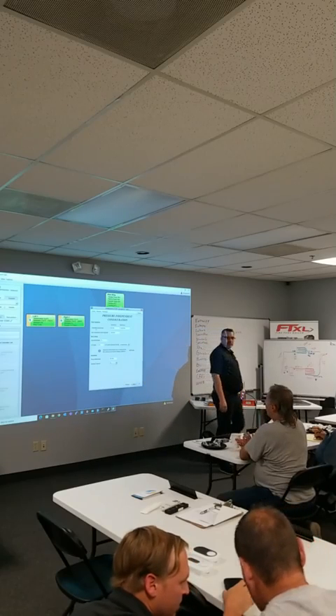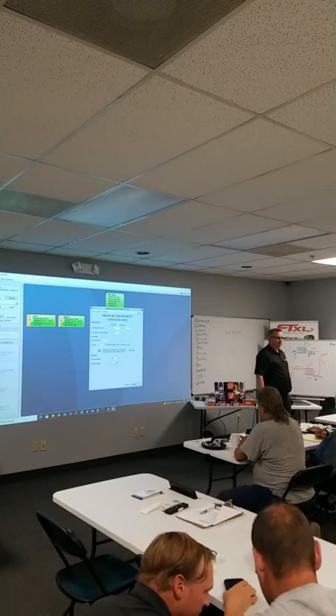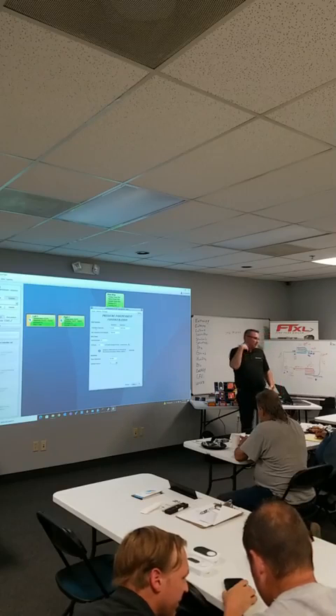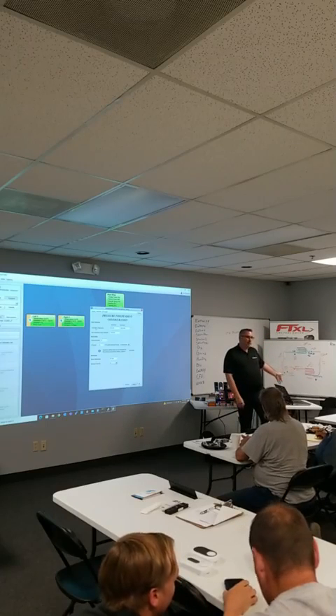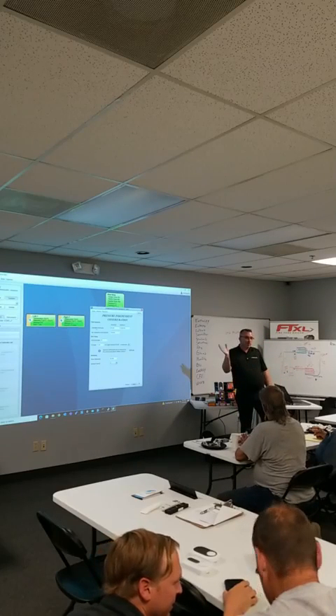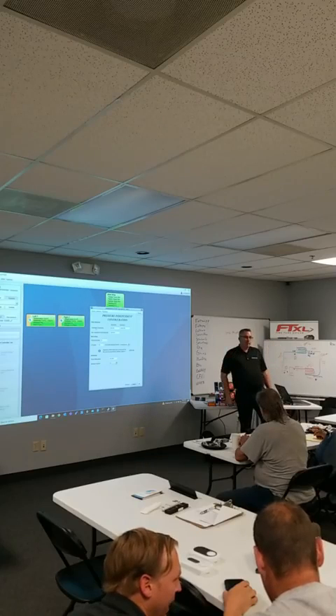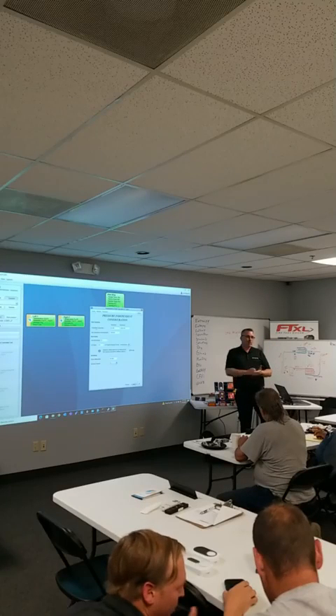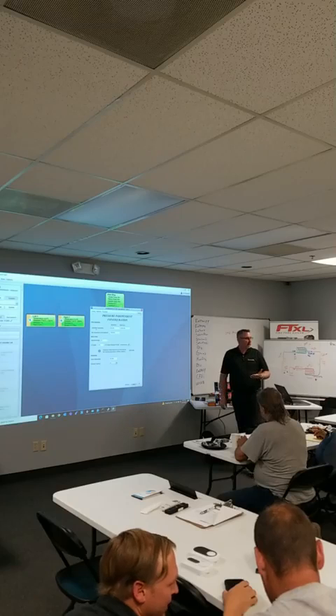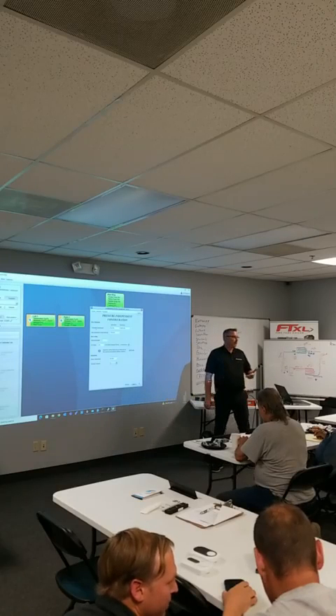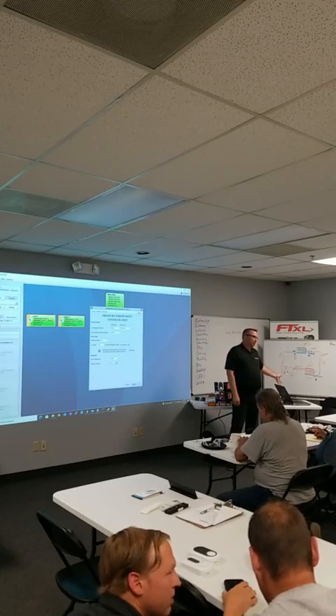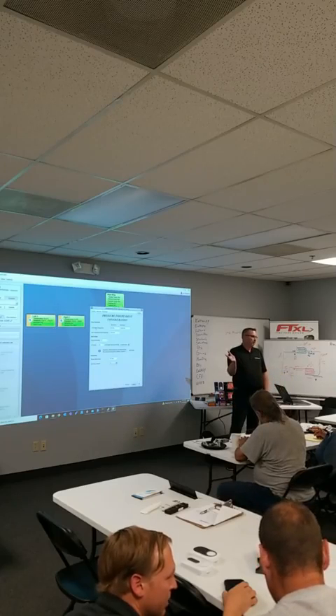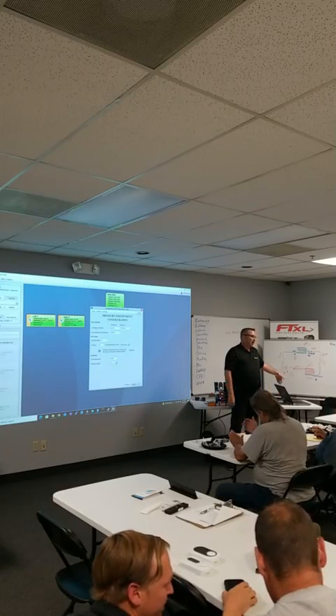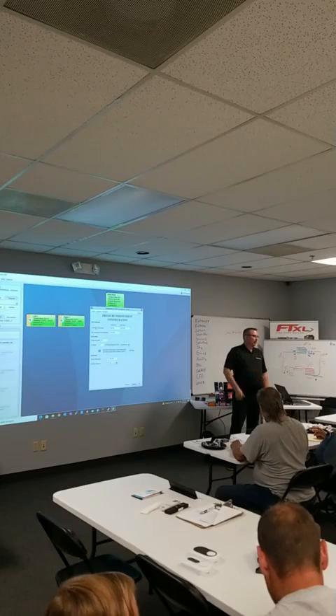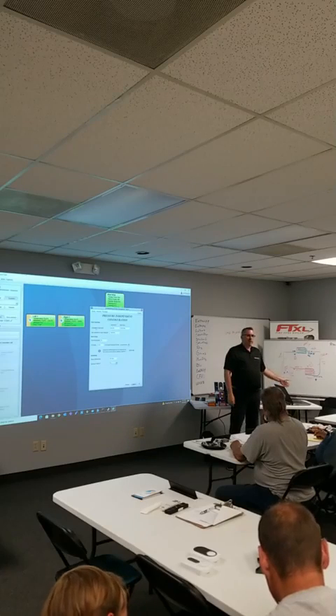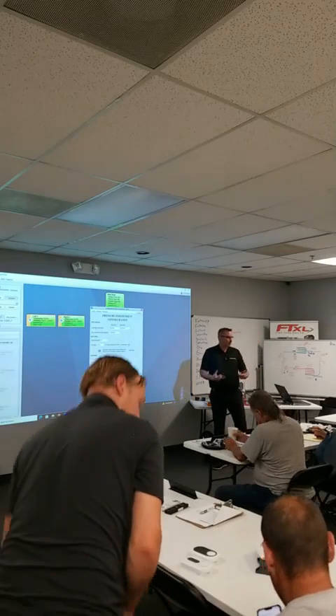I've worked with really good balancers, and then I've worked with some turds. If you work with guys that don't know very well, it's probably better to go through the other step where we run it to high and they read it. But I've worked with guys that'll say, put this K factor in, and I'll put the K factor in, and they'll be like, boom, spot on, got it. But there's other guys that are like, well, I don't know how to calculate the K factor. That's why we put the auto calibrate in, where it'll drive to 100% open. They read it, we write what the CFM is, and then I think it drives to 20% open, they read it, we put the value in, and then it generates a K factor internally.